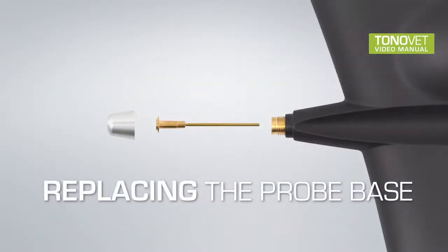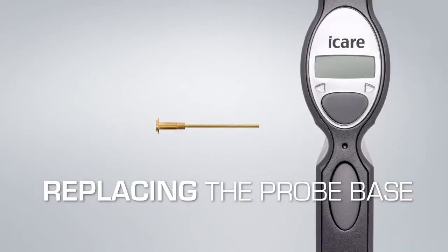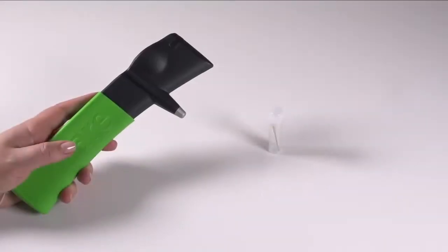Replacing the probe base. During use, some dirt may collect into the probe base, possibly affecting the probe movement. The probe base should be replaced with a clean one every 6 months, or more often if the probe no longer moves smoothly, or the probe base error E01, E02, or E03 is displayed.